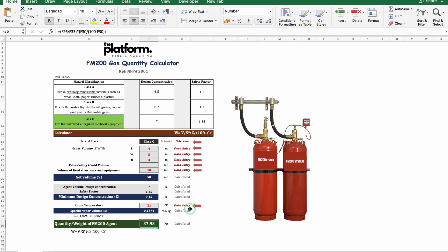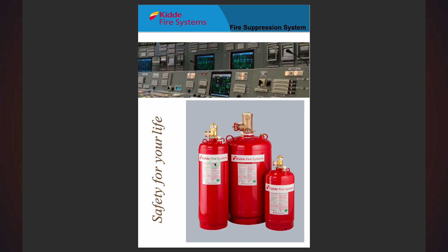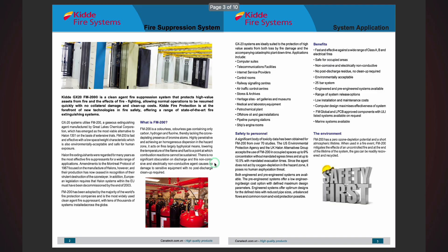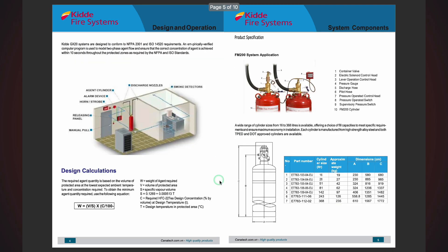The last step is to select a suitable cylinder that can accommodate the desired gas quantity and the discharge nozzles by referring to the manufacturer catalog. This is an example of a Kidde catalog to select the cylinder range. In our example we'll be selecting the third option of cylinders with an approximate weight of 42 kg.